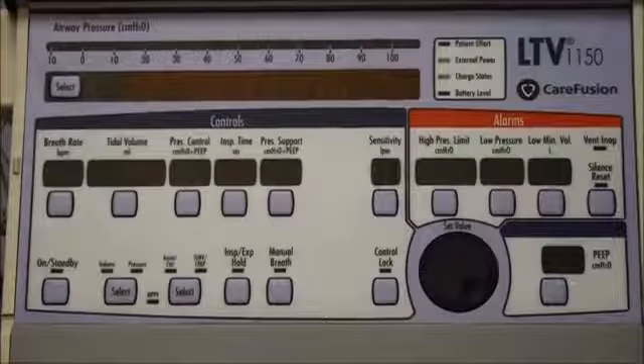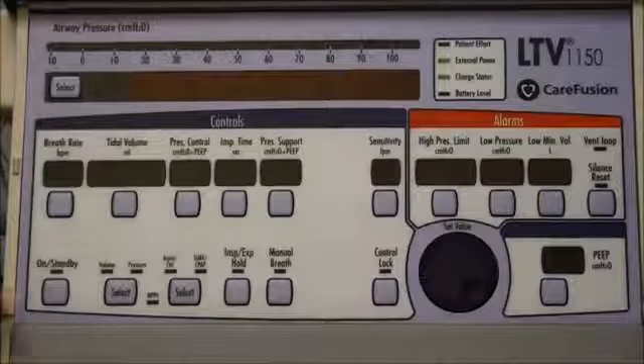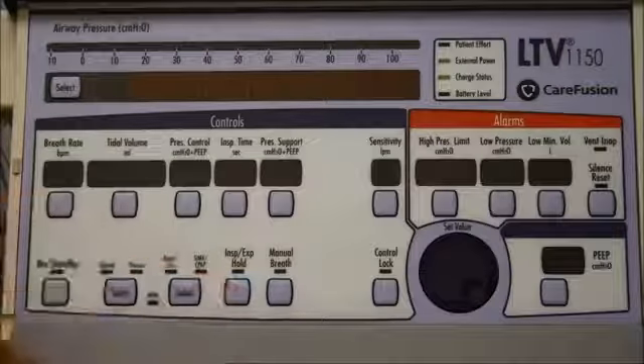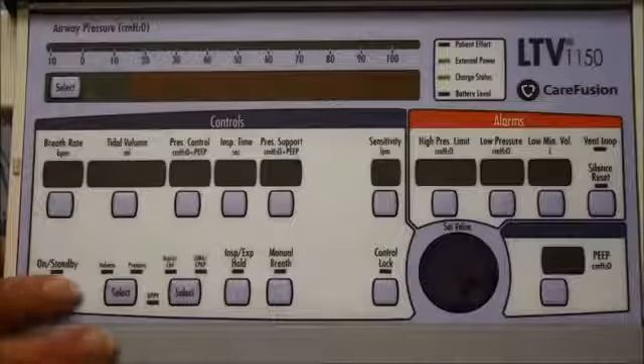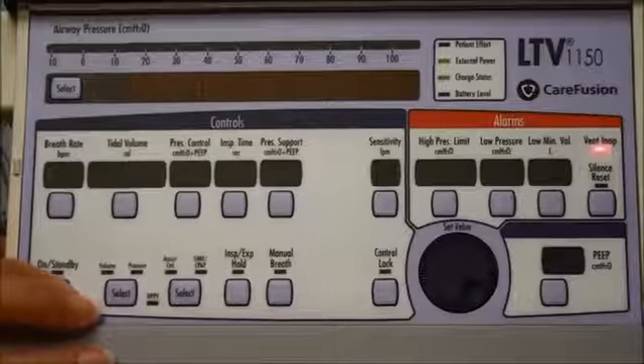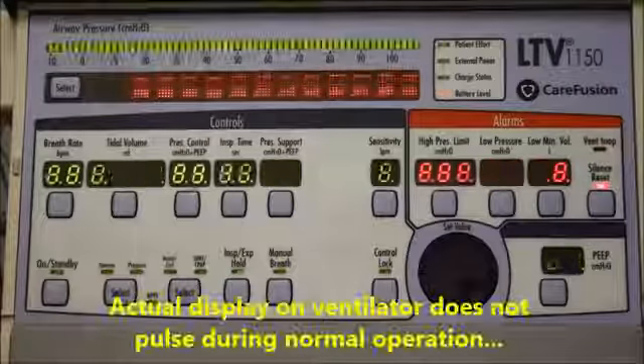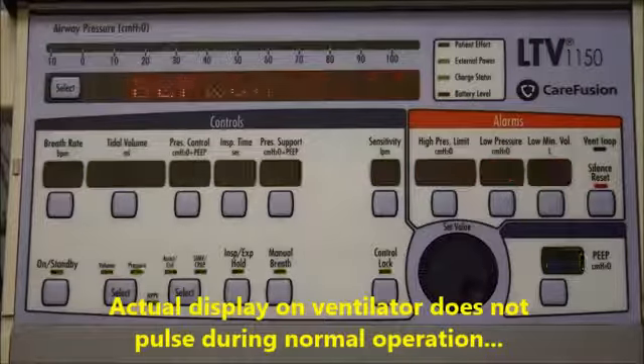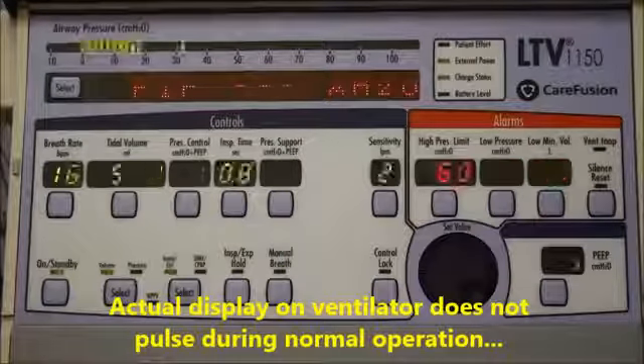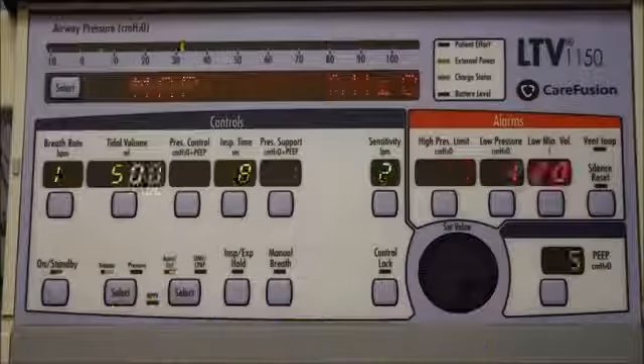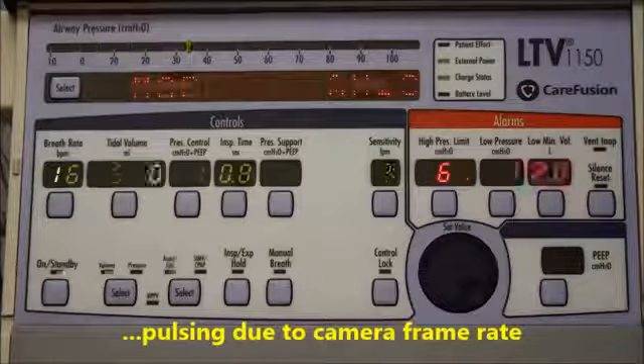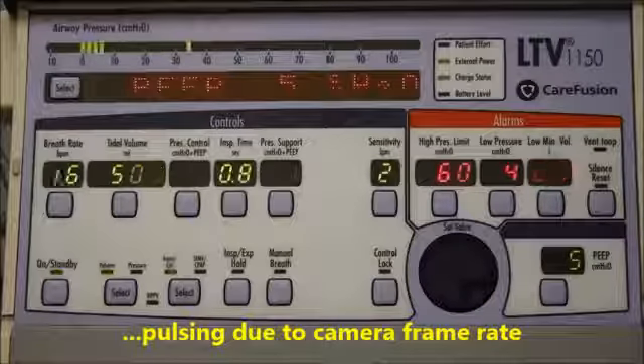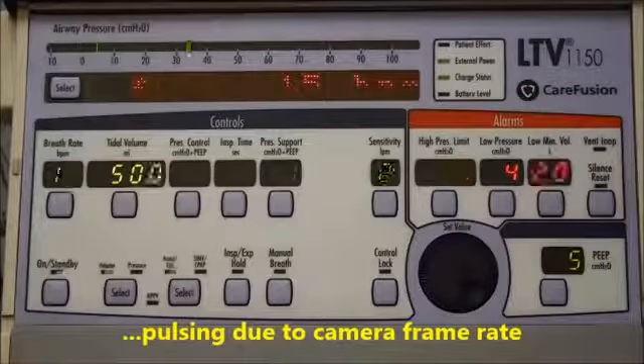Okay, so now I'm going to turn the ventilator on. If you go down to the bottom corner of the control box is your on standby switch. All I need to do is push that button. It'll go through a quick little self-check, and then it'll start ventilating your patient. For demonstration purposes, we have the ventilator hooked up to a test lung.